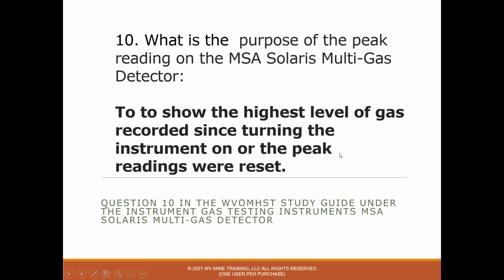Question 10, what's the purpose of the peak reading on the MSA Solaris multi-gas detector? And the answer is that it shows the highest level of gas recorded since turning the instrument on, or since the peak reading was reset. So if maybe you're firebossing and you have an area, maybe it's a 20-foot high roof fall, and you have to check methane gas up in that area, so you put this Solaris on a probe and you extend it up to the top, and when you get it 12 inches from the top, it starts alarming, and you say, oh no, I have methane. So you pull this back down, and by the time you get it back in your hand, it is not in that environment any longer, and it's cleared itself back up. So you don't know how much methane you had above that fall.